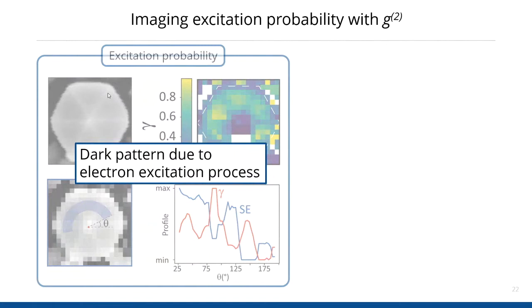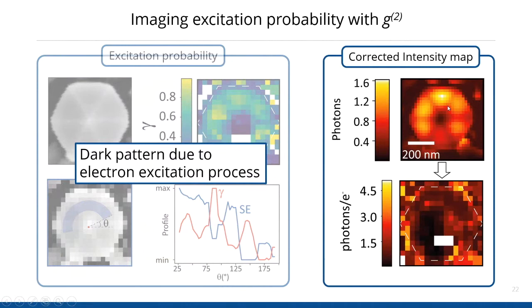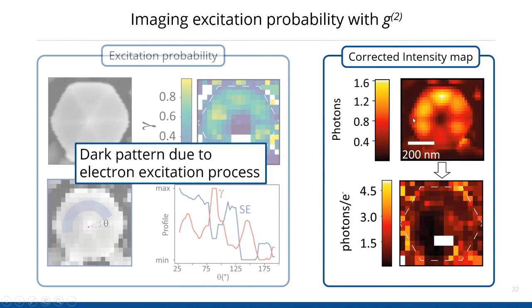If you look at a cathodoluminescence intensity map measured in spectroscopy, you see this faceting and these edges come back in the intensity map. You can correct this with the G2 map, and if you do that, this pattern disappears. That means the intensity variation you see is a geometrical effect related to the electron beam excitation and not necessarily to variations in the material itself. Because you can decouple these things, you can do this without any prior knowledge of the structure — no knowledge of the geometry, and no need for destructive cross-sections by FIB milling. You can just do the time-dynamical experiments with the G2 to obtain this information.